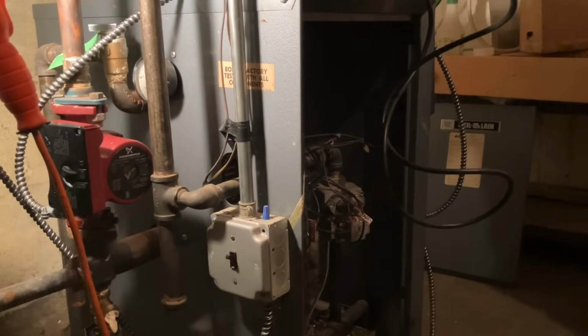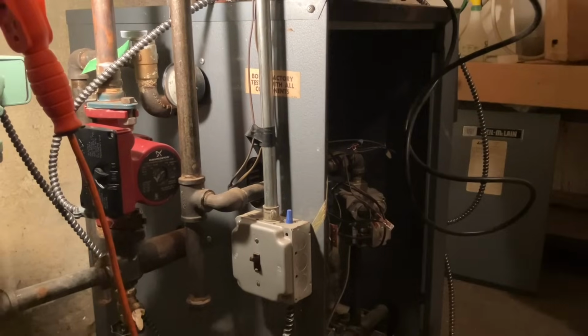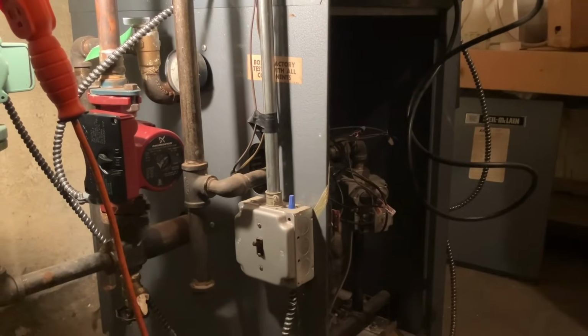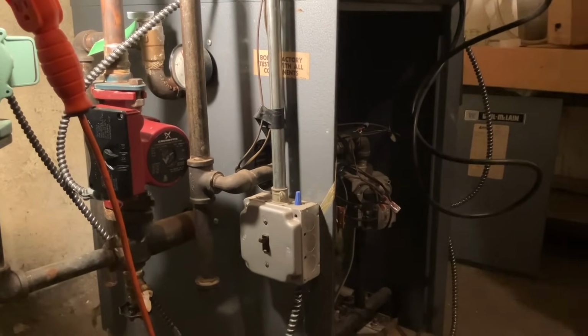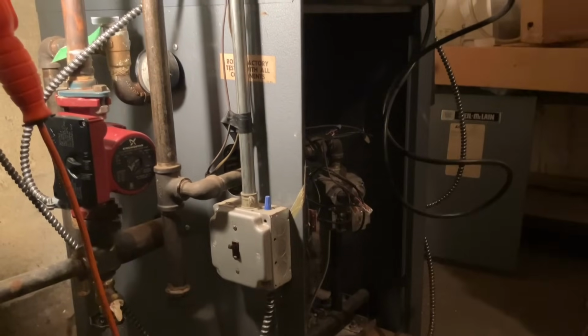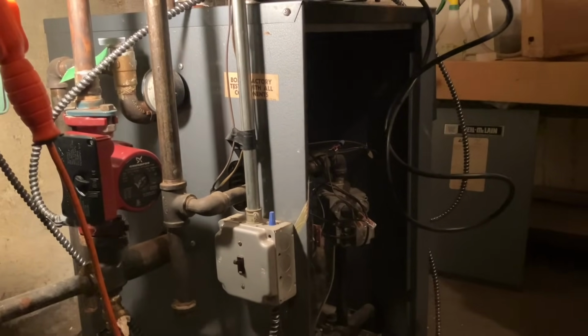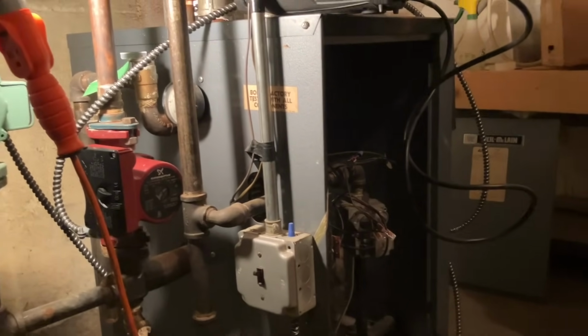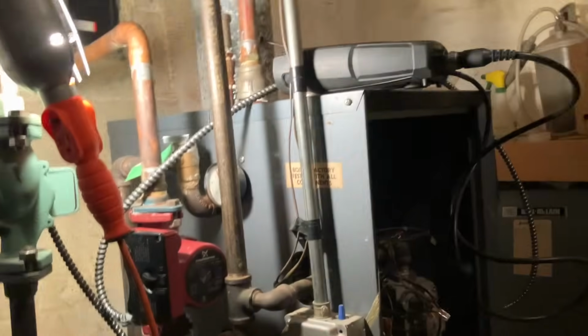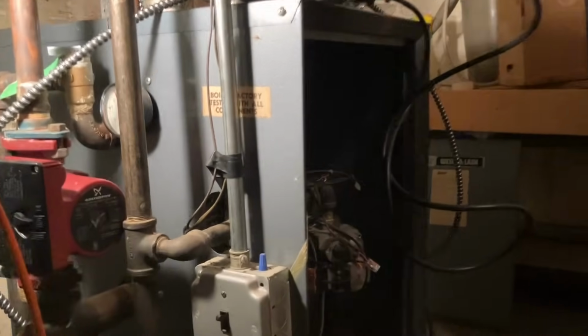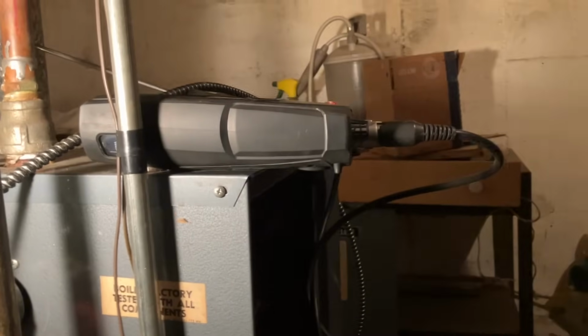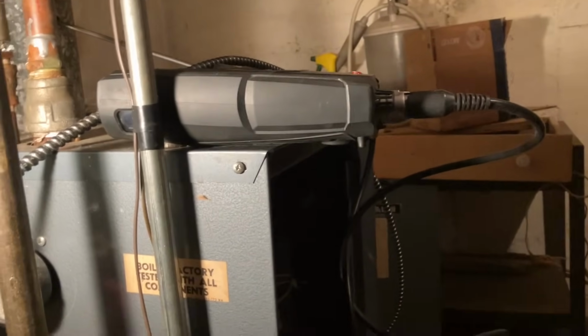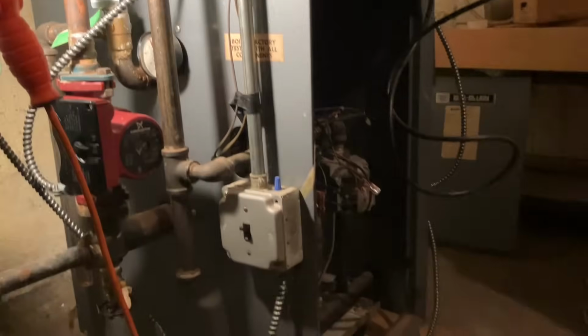I didn't mention 20 degrees. I said 30-degree days. You're saying this is a characteristic for somebody who has baseboard? Yes. It's a characteristic. So characteristic of baseboard, you should have 180 degrees of water. Listen, I could theoretically give you a tankless combi here, a high-efficiency boiler that modulates, that condenses, that doesn't use your chimney, that gets rid of this water heater, gets rid of this boiler, and it's one box that conveniently sits like one of these pieces of wood right there on the wall, connected to everything. It's so efficient, you don't need to expel the flue gases. Well, you have to go outside with the exhausts anyway, but it doesn't need a chimney, right? It's very efficient as that.